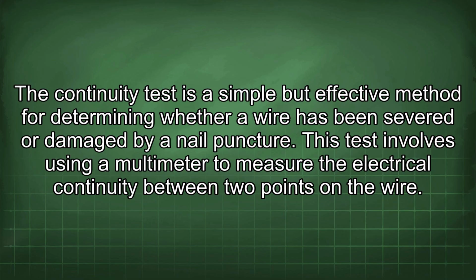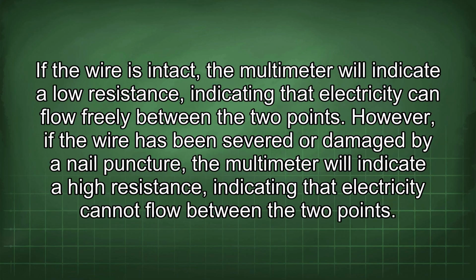The continuity test is a simple but effective method for determining whether a wire has been severed or damaged by a nail puncture. This test involves using a multimeter to measure the electrical continuity between 2 points on the wire. If the wire is intact, the multimeter will indicate a low resistance, indicating that electricity can flow freely between the 2 points. However, if the wire has been severed or damaged by a nail puncture, the multimeter will indicate a high resistance, indicating that electricity cannot flow between the 2 points.